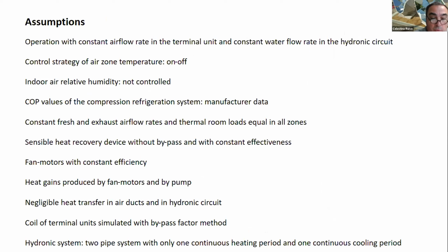Several assumptions were considered. I am just mentioning some of them. Airflow rate and water flow rate were assumed to be constant. Control strategy of air zone temperature implemented with an on-off fan operation of the terminal unit. Sensible heat recovery device was considered, but without bypass, as I mentioned before. A constant effectiveness value was assumed because airflow rates are constant. For the same reason, constant efficiency values were assumed for fan motors.